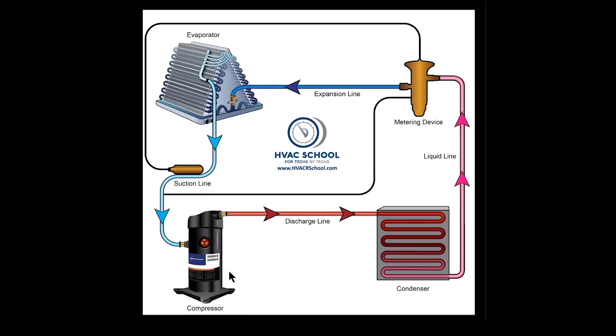You have a compressor that's sitting there pumping away, forcing against this restriction. But the compressor is pulling from somewhere in order to pump out. So if you're not moving refrigerant — and therefore not moving a significant amount of heat down the suction line — then you don't have the refrigerant density going into the compressor, and you're also not going to have as much refrigerant going out. That's why when you have a restriction, you'll see head pressure go up for a little bit, and then slowly dive down along with the suction pressure.